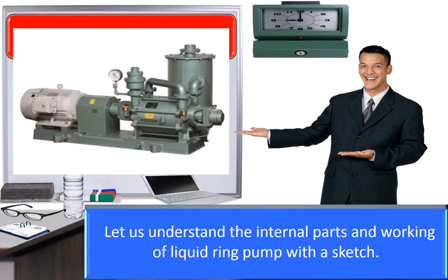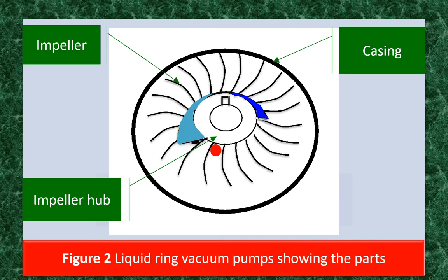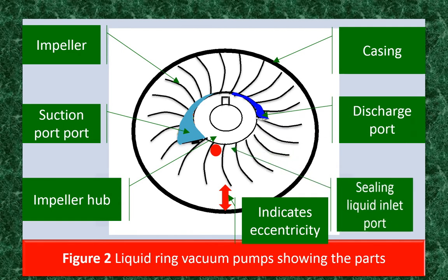Let us understand the internal parts and working principle of a liquid ring vacuum pump. A liquid ring pump has an impeller with blades attached to a center hub, located in a cylindrical body but offset from the center. Note: the casing or pump body is eccentric with the impeller hub. The impeller sits between two end plates called port plates, which have shaped holes called ports. The light blue shaded area is the suction port, the dark blue shaded area is the discharge port, and the red dot at the center is the sealing liquid inlet port.